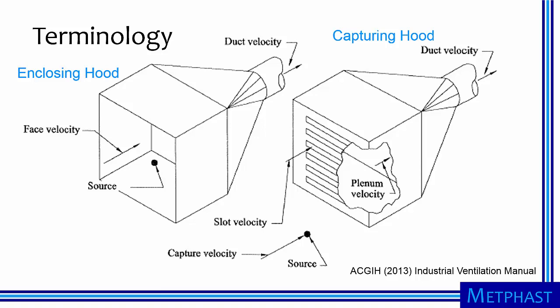A few terms are needed before starting. We've already introduced duct velocity, which when multiplied by duct area gives us air flow. As shown at left, the source is fully or partially enclosed in an enclosing hood. Typically, the face velocity is specified for these hoods to ensure contaminants from the source do not enter the workplace. As shown at right, the source is located outside of a capturing hood. In this case, the velocity of the air at the source, referred to as the capture velocity, must be sufficiently high to pull the contaminant into the hood. Oftentimes, capturing hoods use slots to ensure adequate capture velocity across a wide area. If so, the velocity of air entering the slot — the slot velocity — and the velocity downstream of the slot — the plenum velocity — are usually specified.